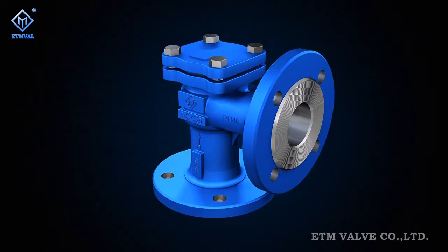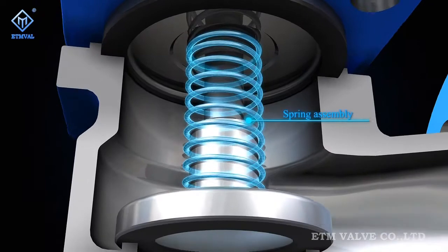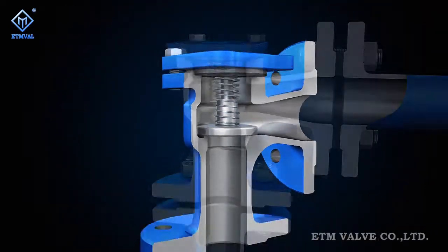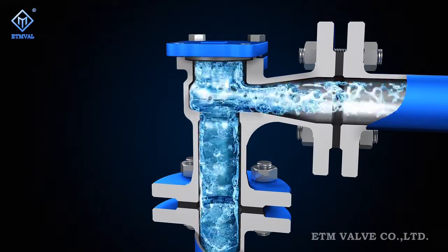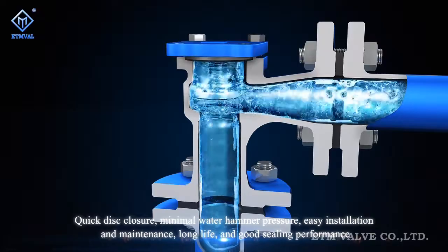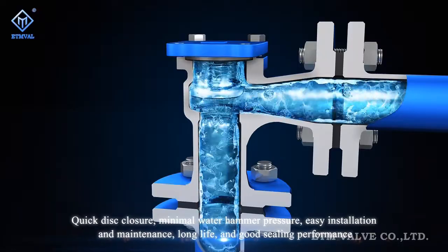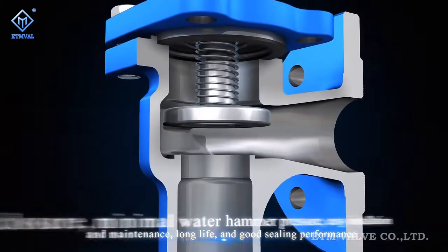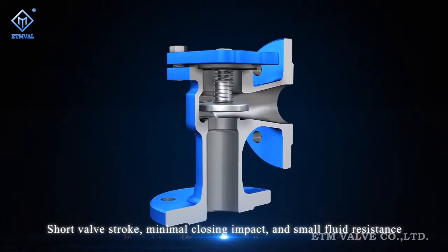Figure C56 series angle pattern lift check valves use a spring structure inside to improve their reliability and practicability in preventing medium backflow, pump and drive motor reversal, and discharge of medium from vessels. This series features quick disc closure, minimal water hammer pressure, easy installation and maintenance, long life, good sealing performance, short valve stroke, minimal closing impact, and small fluid resistance.